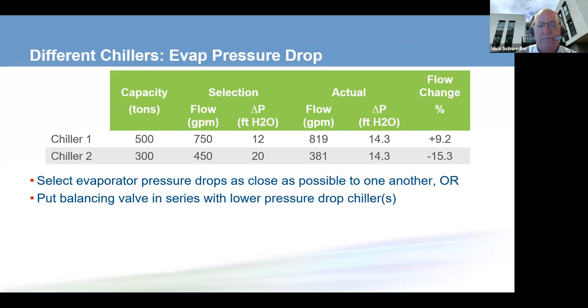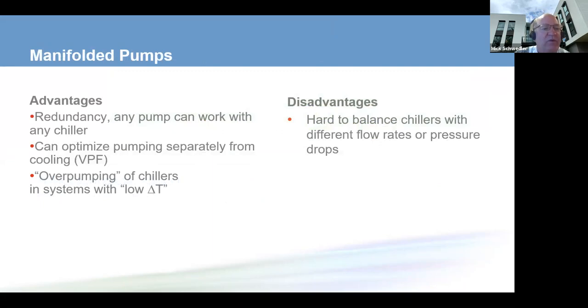So we talked about the advantages and disadvantages of manifolded pumps. Frankly, in variable primary flow systems, I see manifolded pumps used a lot. But with identical chillers, it's a lot simpler than if you have either different capacity chillers or chillers with different pressure drops.